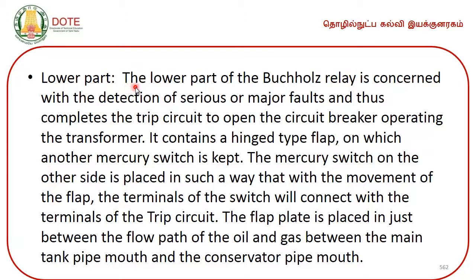Then comes the lower part of the Buchholz relay. The lower part of the Buchholz relay is concerned with the detection of serious or major faults, and thus completes the trip circuit to open the circuit breaker operating the transformer. It contains a hinged type flap on which another mercury switch is kept. The mercury switch on the other side is placed in such a way that with the movement of the flap, the terminals of the switch will connect with the terminals of the trip circuit. The flap plate is placed just between the flow path of the oil and gas between the main tank pipe mouth and the conservator pipe mouth.